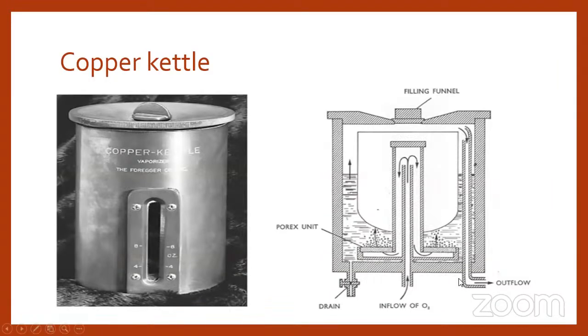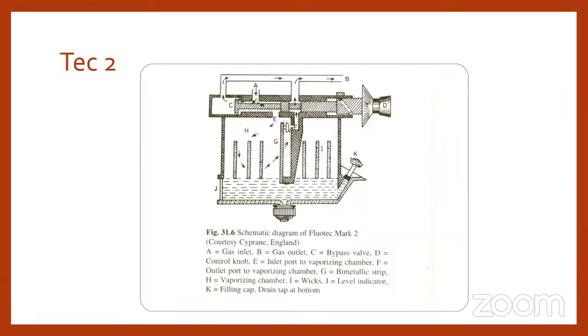and they burst out and release oxygen mixed with the anesthetic agent, and this mixture will be passing through this pipeline and it will come out of the circuit to the patient through this outflow valve. And if the fresh gas flow is reduced, the sudden anesthetic concentration may be dangerously delivered to the patient in this kind of vaporizer. So later on, this was omitted. From then, with advancing time, they have incorporated various safety measures to develop the vaporizer so that the vapor concentration that is delivered to the patient will remain the same.